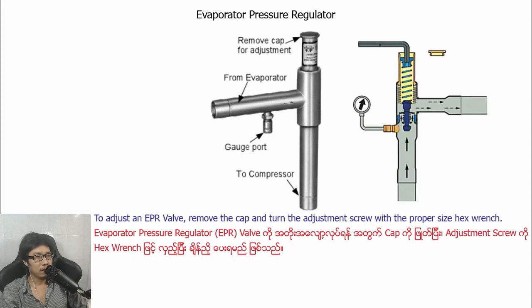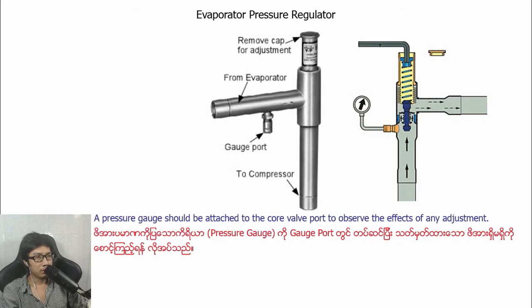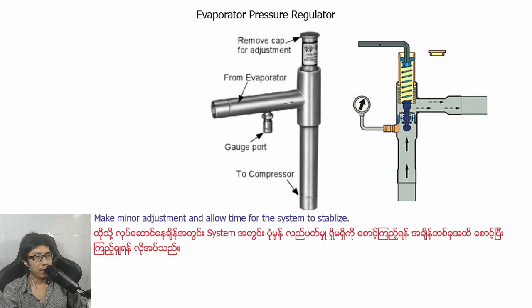To adjust an EPR valve, remove the cap and turn the adjustment screw with the proper size hex wrench. A pressure gauge should be attached to the core valve port to observe the effect of any adjustment. Make minor adjustments and allow time for the system to stabilize.